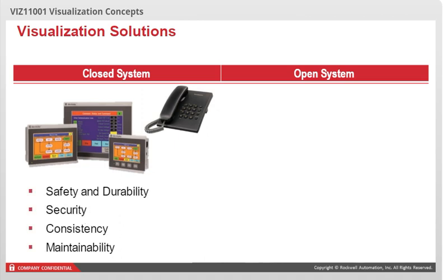Dedicated HMI devices provide some unique advantages in manufacturing. They are tested to very specific global standards, industrial environments, and temperatures. For security, with specially constructed operating systems, these devices are also much less susceptible to viruses or malware. In fact, many units require no antivirus software to be installed at all. Dedicated devices are designed to run for extended periods of continuous runtime. Once a design has been implemented with enough capacity to withstand anticipated growth and application evolution, the expectation is that future investments in the same product will behave in the same manner. This is not necessarily true for commercially available computers with off-the-shelf operating systems.